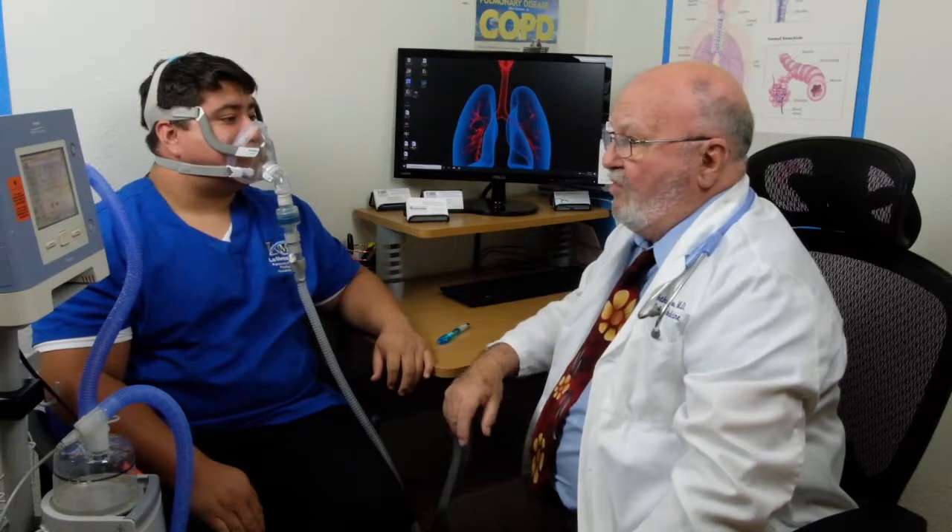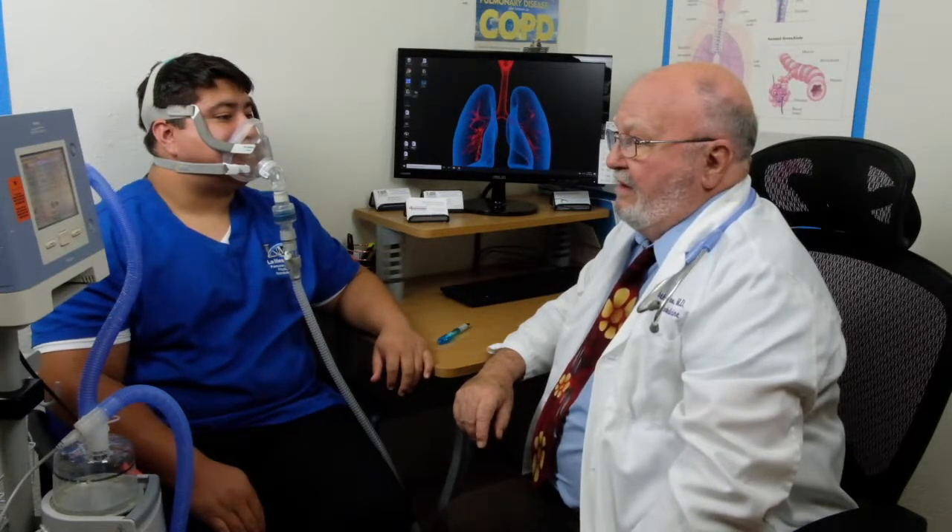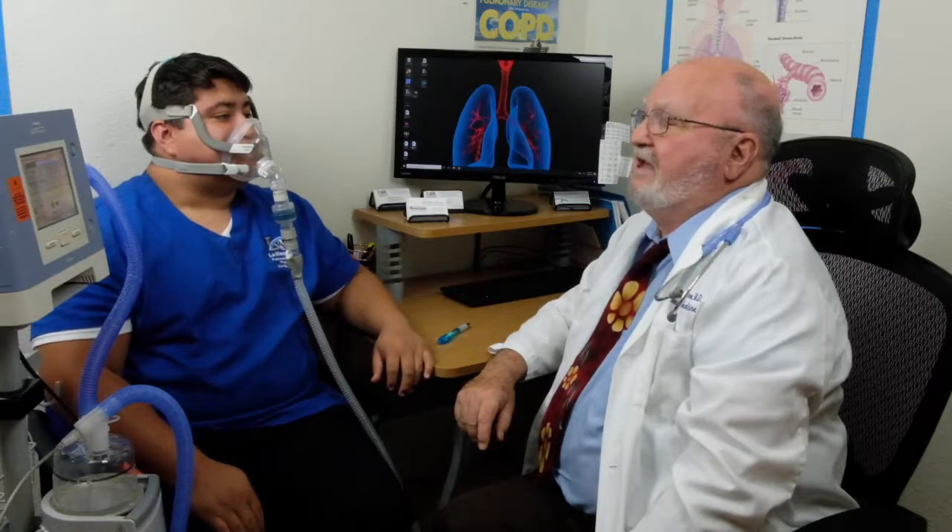He's taking a normal breath now, and now the assisted breath is functioning. The assisted breath is set at 10 breaths per minute, so he will breathe at approximately 14 to 16 breaths per minute, 10 of which will be assisted volume.